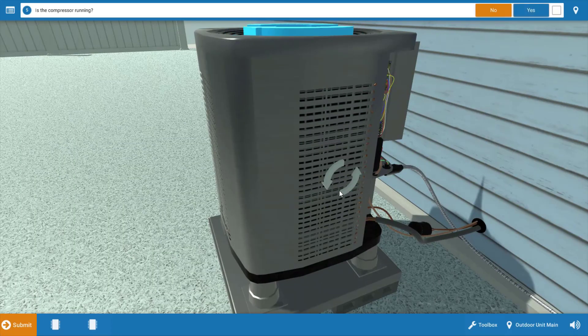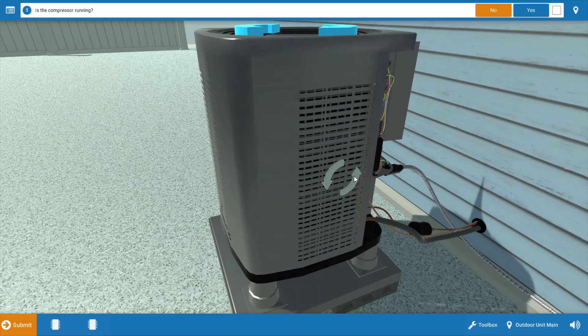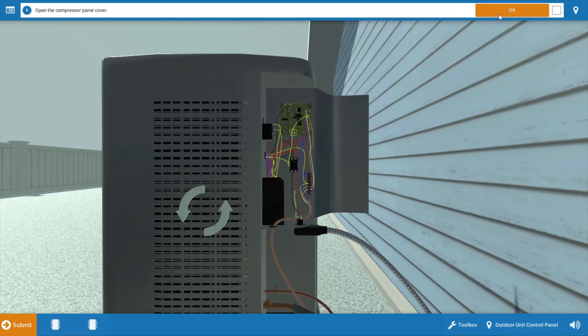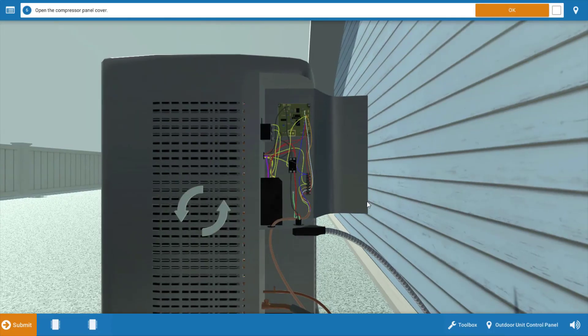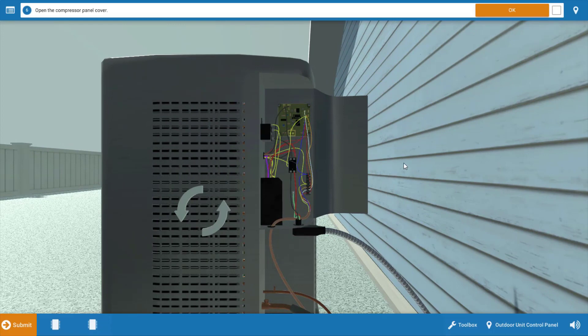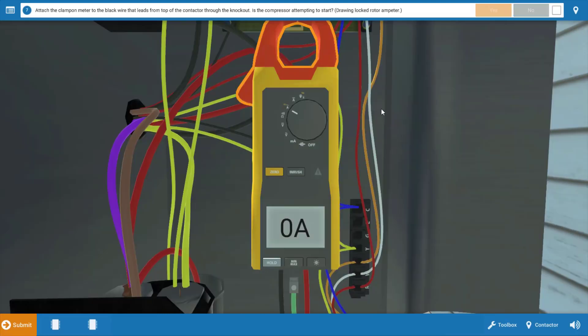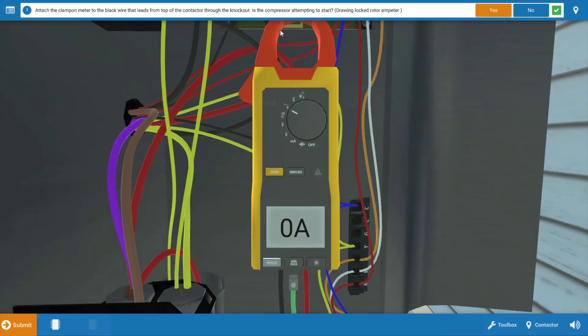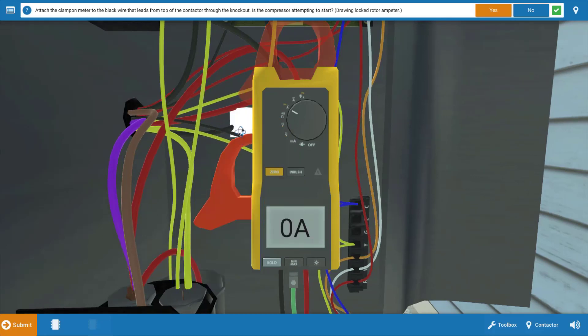Now, it appears that the compressor is not running, so we're going to click no, but it may be cycling on locked rotor amperage, so we're going to need to check this with a clamp on ammeter. So click OK on the procedure guide and take your clamp on ammeter and place the jaws of it around the common wire of the compressor, which is this glowing orange hotspot right here.